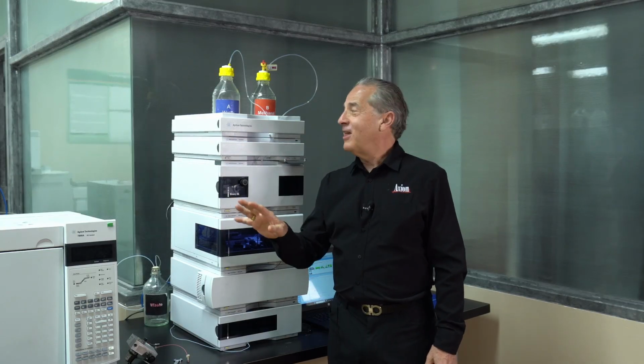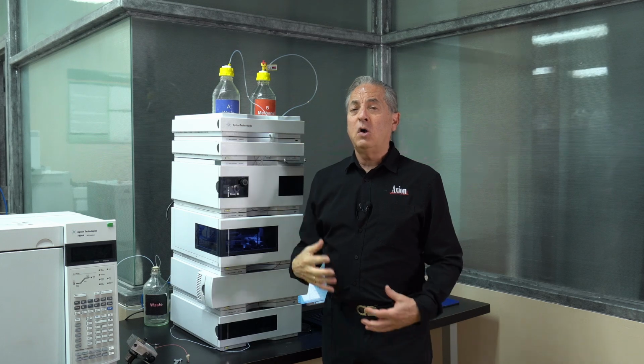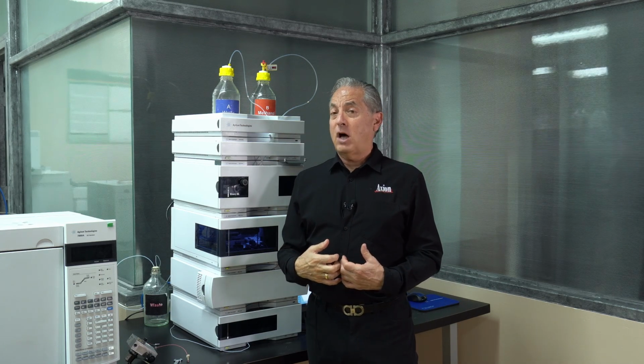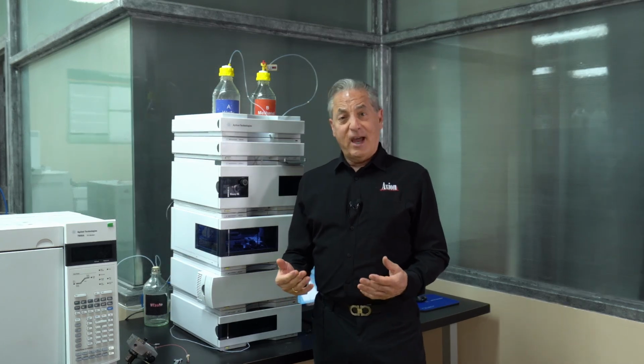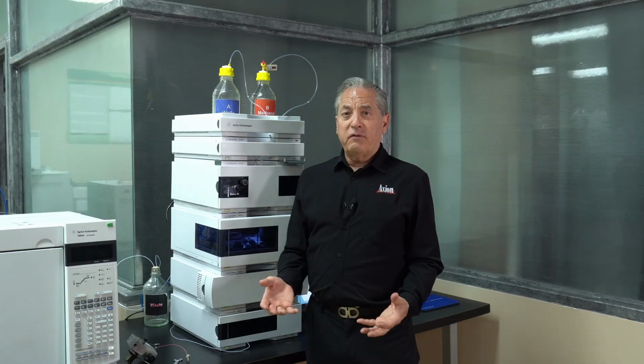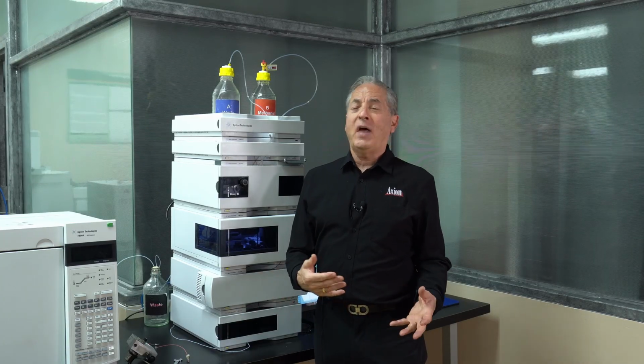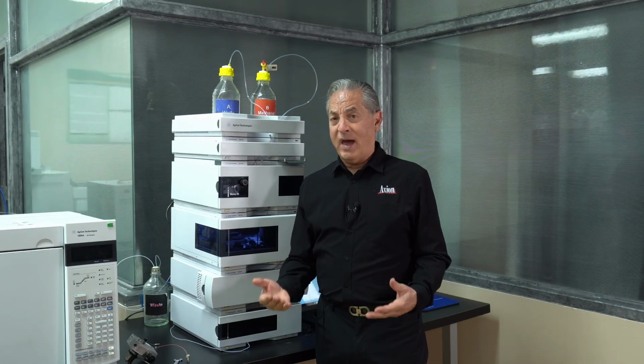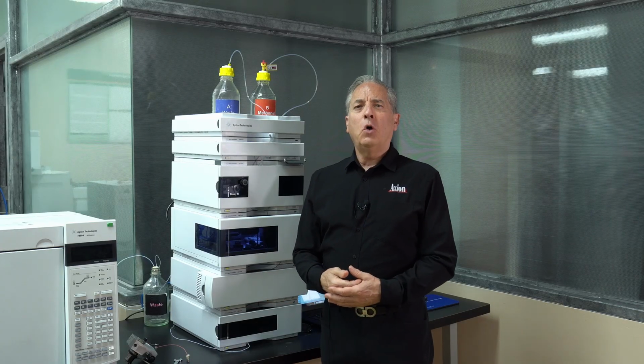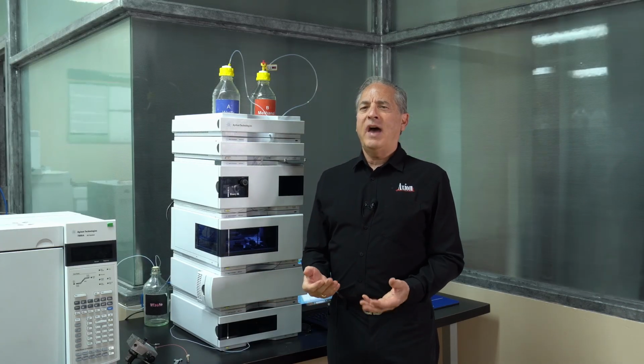Number 12 is a little different than the rest. So you get the idea that water should have some kind of a, I'll call it a preservative in it. Now you've got to be careful. You can't add regular preservatives because they contain UV chromophores. You'll add problems. You'll add impurities to your baseline. So I've always been a big fan of adding some biocide.